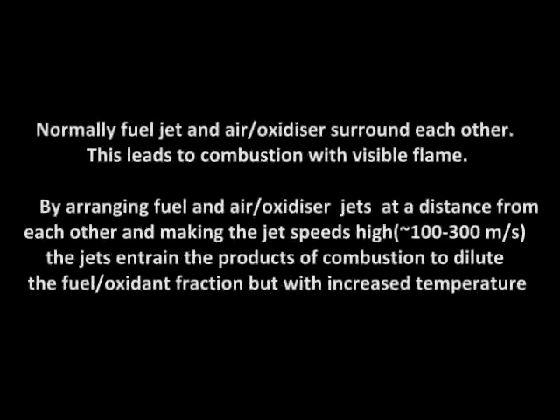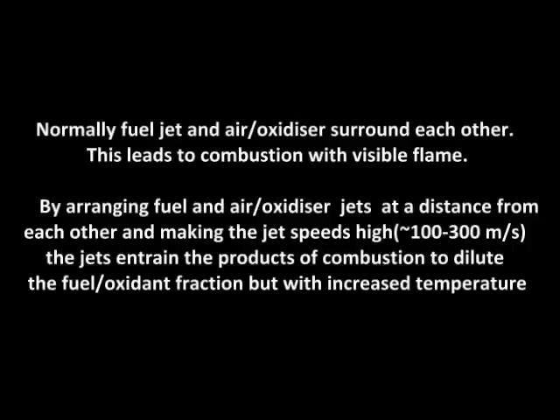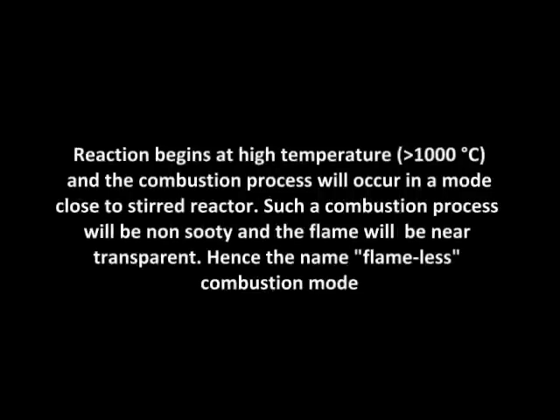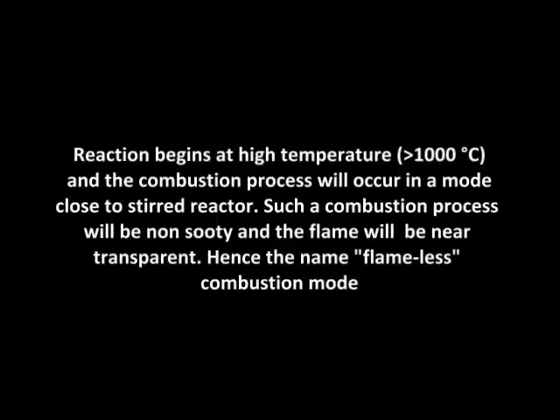Flameless combustion. Normally, fuel jet and air oxidizers are around each other, leading to combustion with a visible flame. By arranging the fuel and oxidizer jets at a distance from each other and making the jet speeds high — of the order of 100 to 300 meters per second — the jets entrain high-temperature products of combustion, diluting the fuel and oxidizer fractions while increasing the temperature of the jets. Reaction begins at high temperature, typically 1000 degrees centigrade or more, and the combustion process occurs in a mode closer to a well-stirred reactor. Such a combustion process will be non-sooty and the flame will be near transparent — hence the name, flameless combustion mode. The high-speed jets on the right are for flameless combustion.